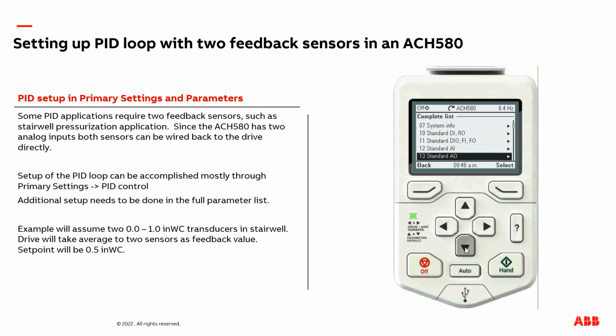The next adjustments are going to be made in group 40. Here you can see we have one of the feedback sources connected to analog input 2. We now need to set up the other one to analog input 1, scaled. We want to make sure we do scaled and not percent, because we want to make sure that we're following the 0 to 1 inch of water column setting.